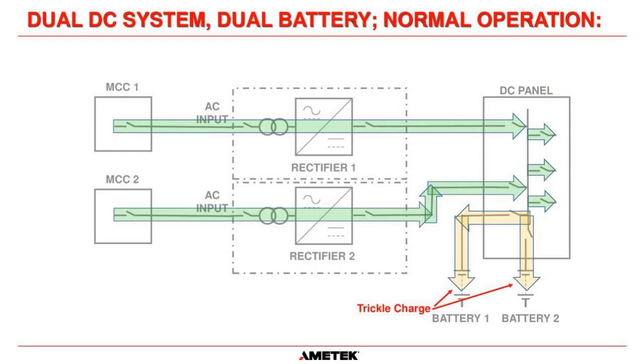But what's critically important, and people forget this, remember, the reason you have a charger connected to your system is to keep the batteries charged. And the battery needs to be charged at a specific voltage. So let's say this is 135 volts. We want the other battery to be charged at 135 volts. But once again, we have to measure this at the positive and the negative of the battery itself, and cable drops and everything will come back into the situation. So there could be a possibility for us to keep both batteries at 135 volts, but because of cable drops, maybe this one here needs to be 136 volts, and this one here needs to be 135 to maintain this 135 volts at the battery. And therefore, this charger here is going to supply more current to the load circuits because it has the higher voltage.